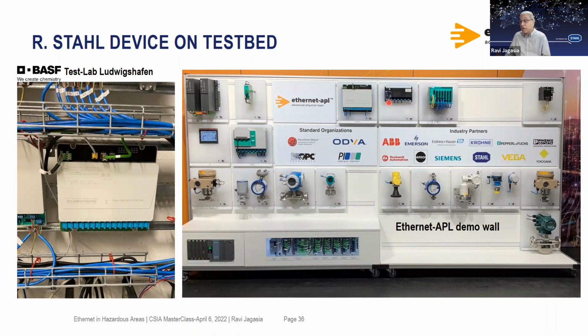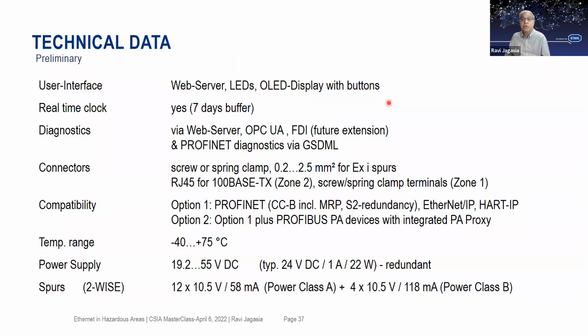So in conclusion to the product that I showed you, what are the features you would see? You do have a real-time clock, you have a web server for local diagnostics and LEDs and displays available. You could have OPC, FDI, that is the PA-DIM, and all those new expected field device drivers available, which will be incorporated. You can do a lot of PROFINET diagnostics if you opt for the PROFINET version. So there will be multiple options over there. You see that the PROFINET version or the Profibus PA version or the standard Ethernet-APL version.